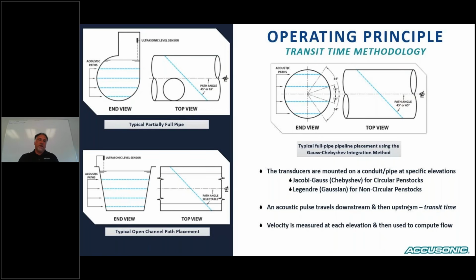And then on the left here, we have typical partially full applications. This isn't typical for the hydro market, but we do this for other industries such as irrigation, et cetera, as well as potentially doing power canals. So the trapezoidal or rectangular section would be kind of for a power canal situation. So the way the technology typically works is we have an upstream transducer and a downstream transducer. We send a pulse that goes with flow and against flow, and the signal travels faster with the flow, goes slower against the flow. That delta T, that time difference, is directly proportional to velocity.